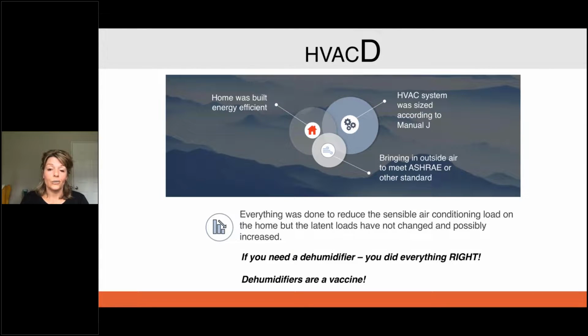I talk to a lot of builders and contractors, and it seems like if I need a dehumidifier, somebody did something wrong. The reality is if you're building the house energy efficient, making it as tight as possible, sizing according to best practices — which is Manual J — and bringing in that outdoor fresh air we need to dilute the indoor air contaminants, then if you need a dehumidifier, you probably did everything right. We just need something to focus on those moisture loads now.